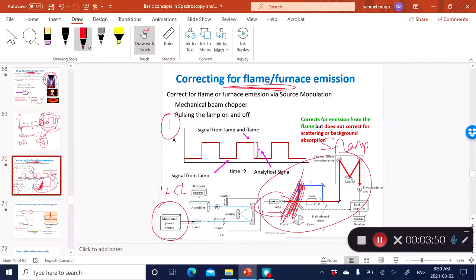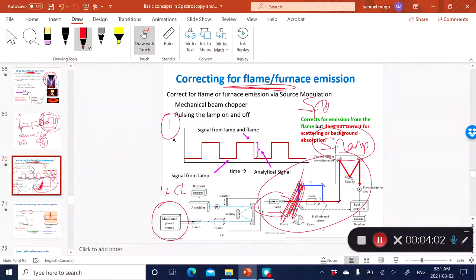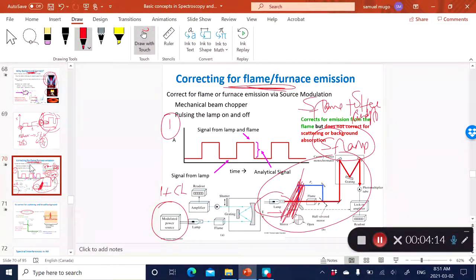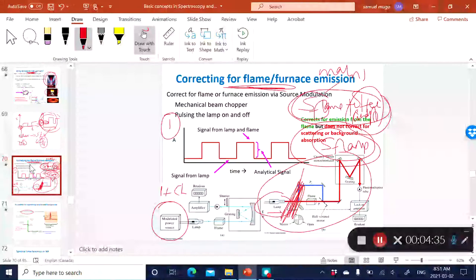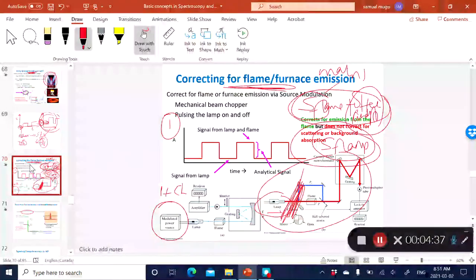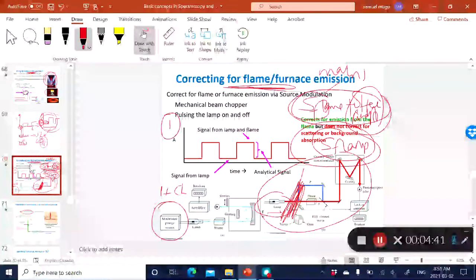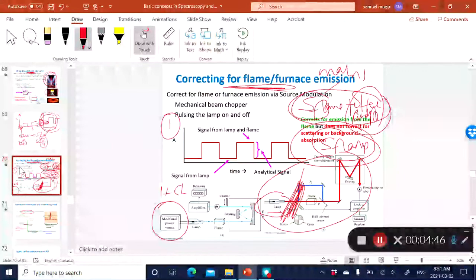When the lamp is off or blocked, the detector is only detecting the signal from the flame. When the lamp is on or not blocked, you're detecting the signal from the flame as well as the signal from the hollow cathode lamp — essentially the analyte signal. This other measurement is the matrix signal. So if you subtract the two, you're only going to get your analyte signal.